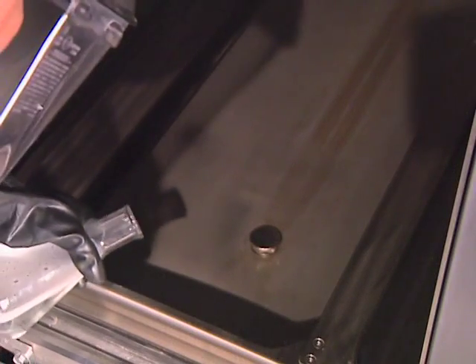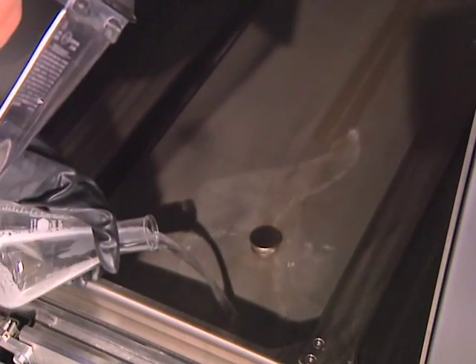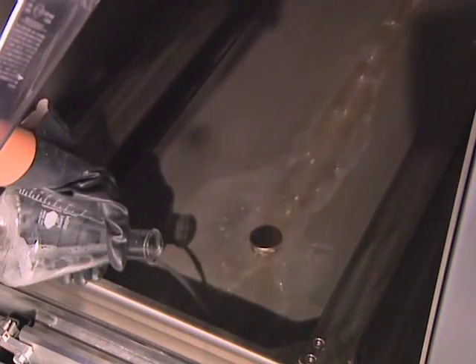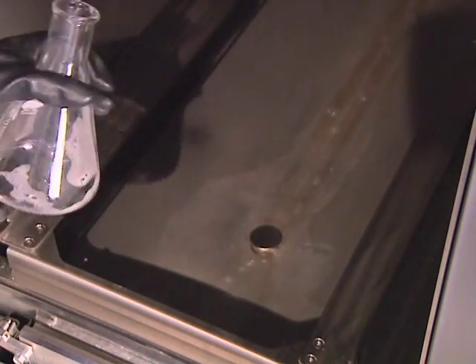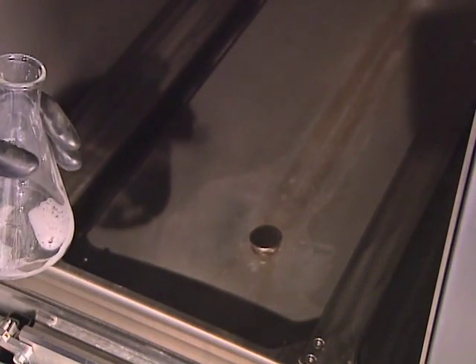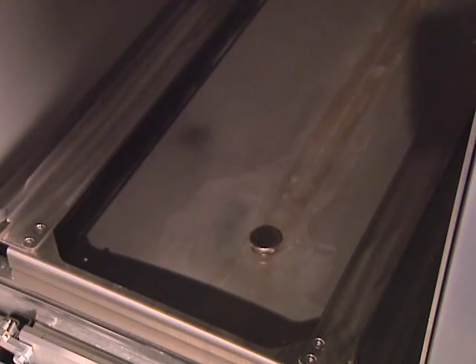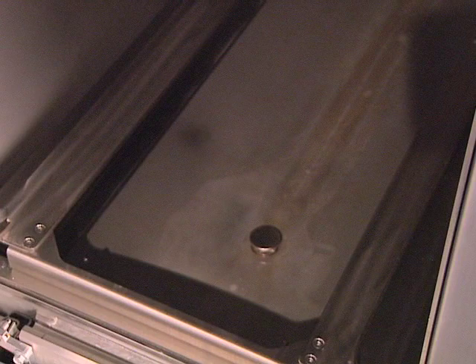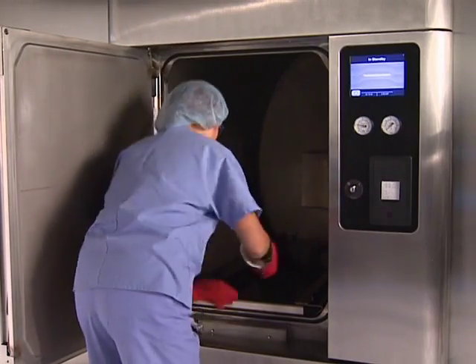Pour a solution of 1 1/4 cup of Liquid Jet 2 instrument detergent and 1 pint of hot water into the drain. If this detergent isn't available, you can use a hot solution of 1 tablespoon of trisodium phosphate to 1 pint of hot water. The solution may puddle in the bottom of the chamber. This is normal and should drain completely within a few minutes. Replace the strainer in the chamber drain.